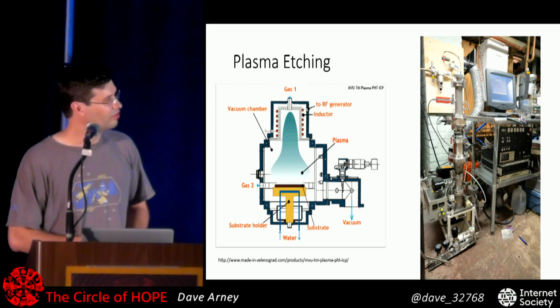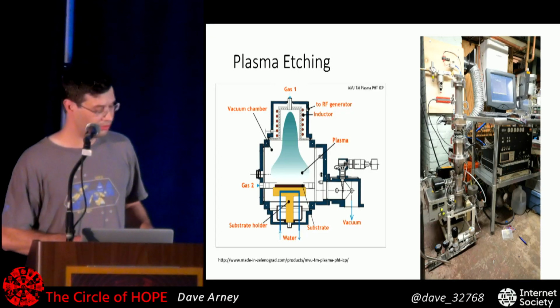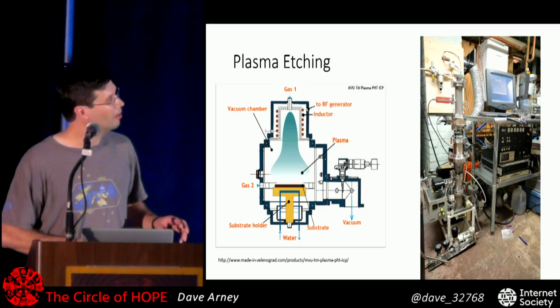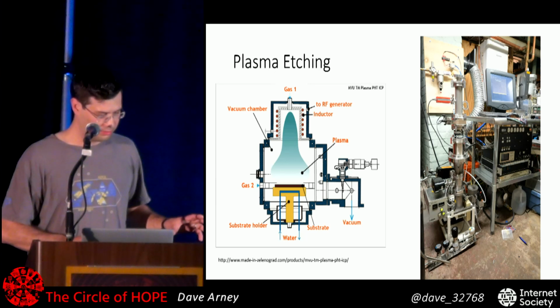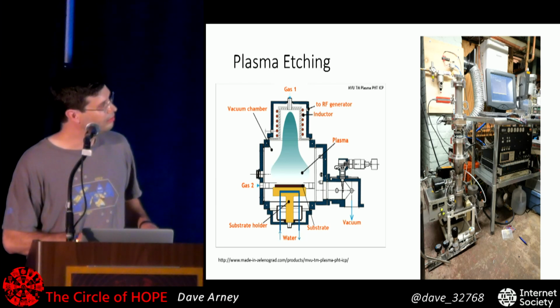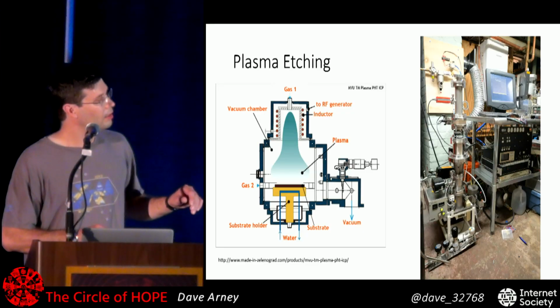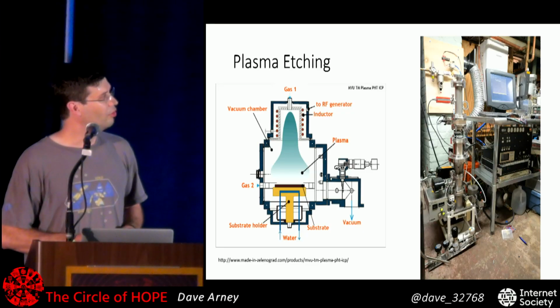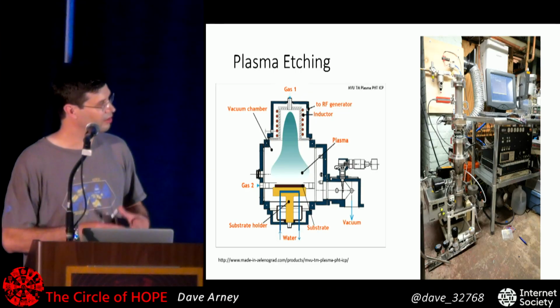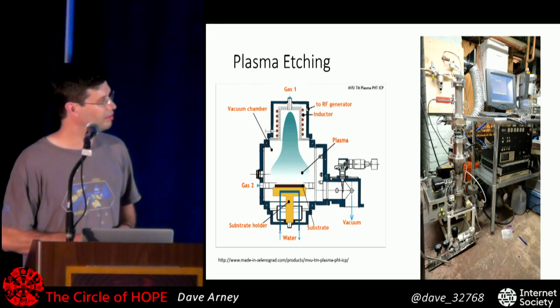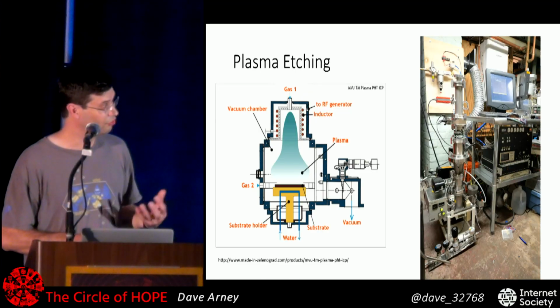Okay, so the plasma etching setup, and on the right is my basement. So this is the setup down there now. On the left here, we've got a plasma etching setup. So here we've got the chamber where you're making the plasma. This is coupled to your larger RF source. There's a coil that goes around there. It's inductively coupled, and so it creates a plasma out of these gases that you're letting in through the top. The ions all shoot down, they're attracted to the chuck, they hit your chuck, whatever chemical reaction happens, and the products, whatever gases you're creating, go out through your vacuum system.